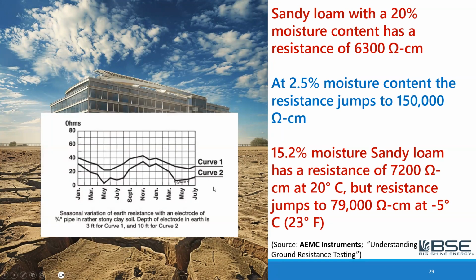This is a curve, again, from two curves from the AEMC brochure, Understanding Ground Resistance Testing. If you look at curve one, you can see that there's a significant variation in climate in the months of the year with the resistance that they obtained with a 3/4 inch pipe in what they call rather stony clay soil. And most of the year it's failing. There was one brief interval, the month of May, where it was barely okay.